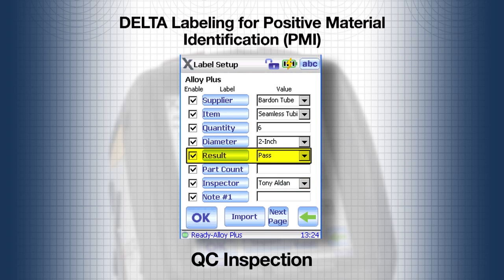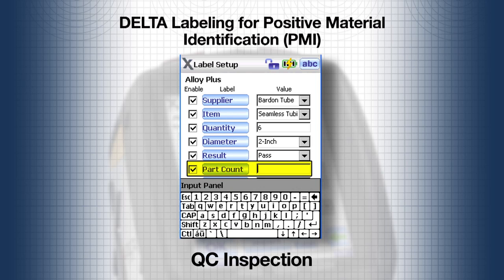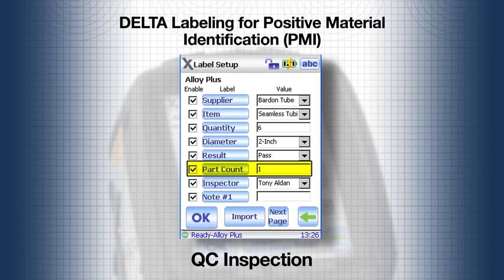Since the default result is passed, it can be left as is. If the item does not pass the test, this field can be changed after the test is completed. Regarding the part count, the Delta can count the number of parts being tested. Setting the part count to one means that the count will start at one. If the part count is left blank, the Delta does not provide a count.